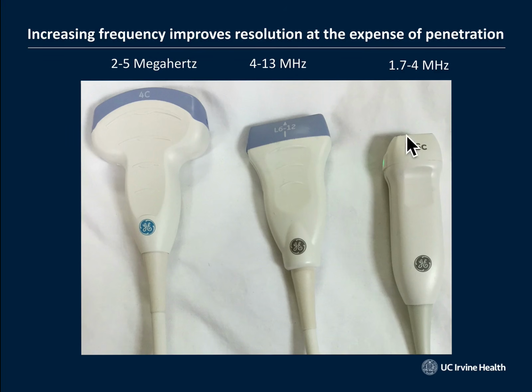This low frequency probe here, think of that like a telephoto lens. You're looking far away into the body in this case. This very high frequency linear probe here has a high frequency bandwidth, so the resolution is beautiful, but it can only see structures up really close, sort of like a macro lens on a camera. And so then you've got this mid-range frequency transducer here, large footprint curvilinear probe, that is sort of a balance between low and high frequencies. So it can penetrate pretty good, but also gets nice, pretty images.